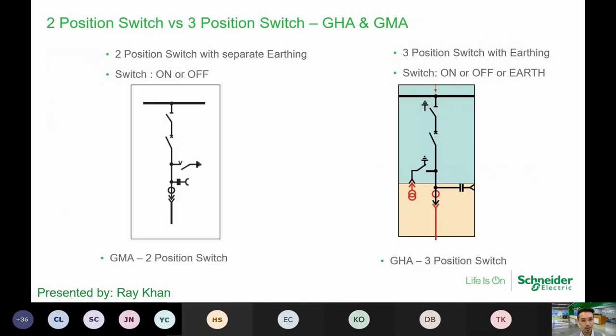185 kV test requirement. Now, there's also a lot of questions in terms of the switching between the single gas tank and the double gas tank. Allow me to explain a little bit here. So the GMA single gas tank works on the two position switch. The GHA double gas tank works on a three position switch. So what's the difference here?